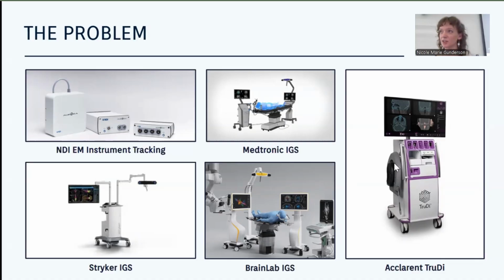Additionally, with electromagnetic tracking, something can happen called registration drift. The way that you align the CT scan with the actual patient's head is by putting a little sticker on the forehead right here, and you trace it with the probe to make sure it's calibrated correctly. But as surgery continues, things are getting bumped, things are getting moved, the sticker's sliding, there's sweat, there's blood, there's liquids, there's saline, there's everything else. The sticker moves, the patient gets moved, things get unregistered, which can increase the baseline 2 millimeter error even more.